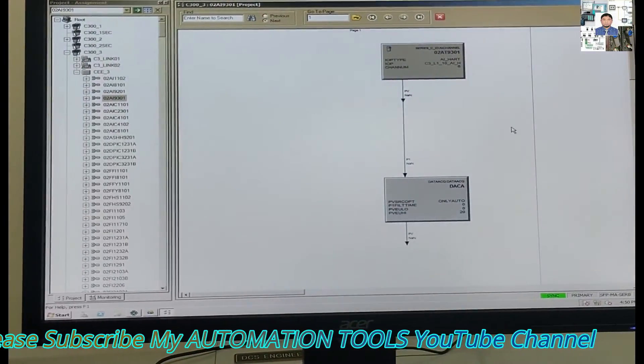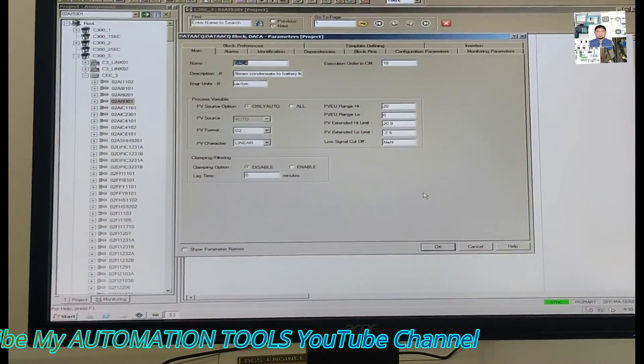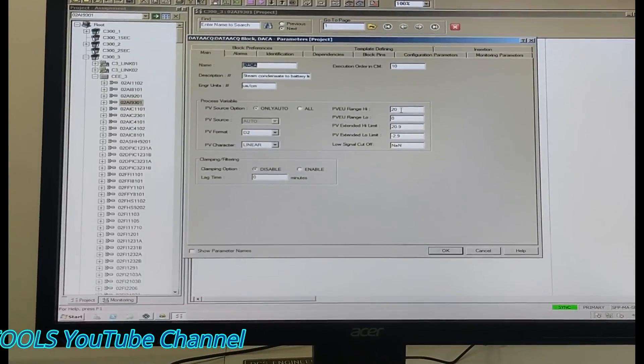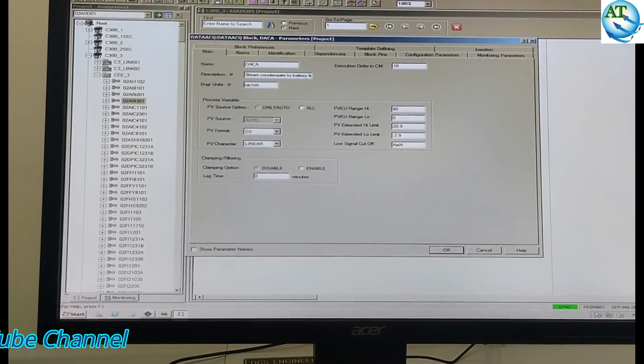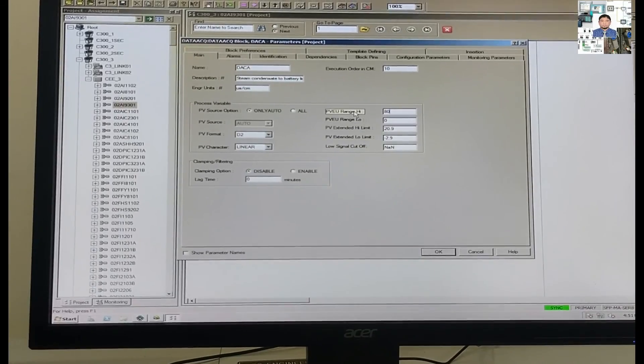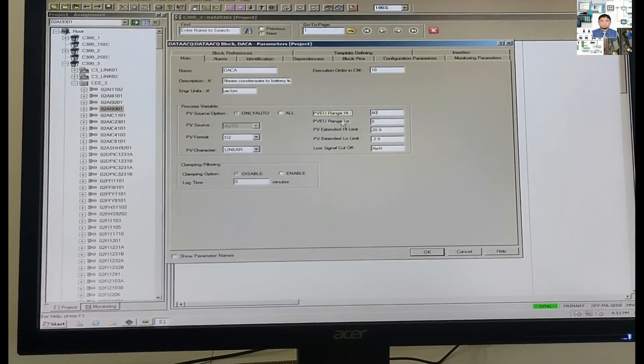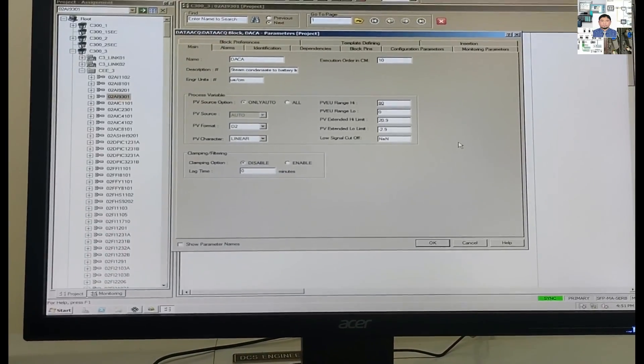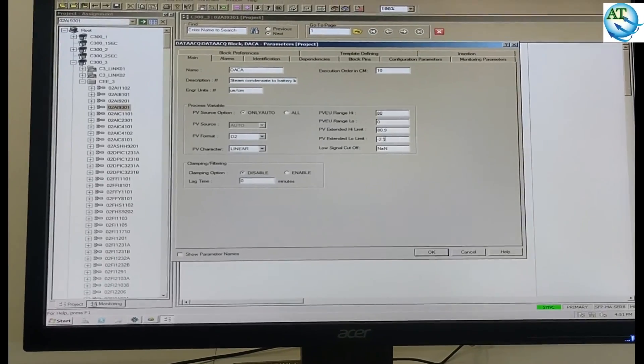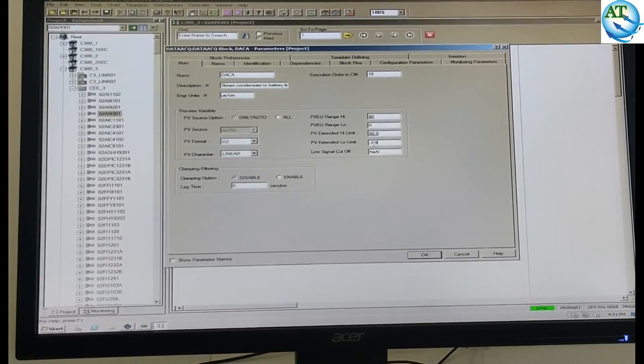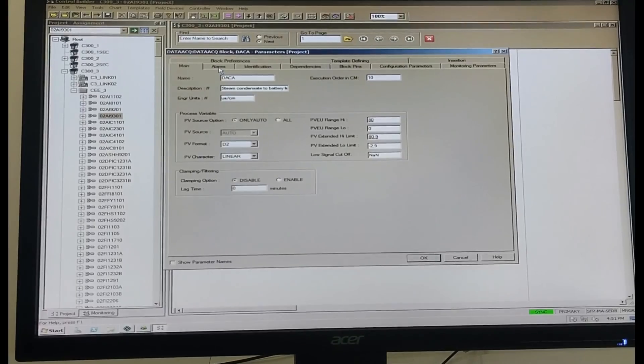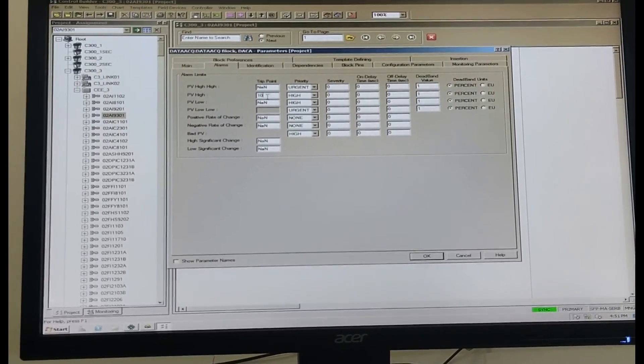In the base program, we don't have to change anything there. So, go to the DACA value where you want to change the range of this transmitter. You see, it is currently showing 0 to 20. We have to change it to 0 to 80. So, we put the 0 to 80 range. At the high extension rate PV — the extended high range — we have to also change it to 80. We don't need to change the PV extension rate low range; we only change the high limit and the extended high limit.